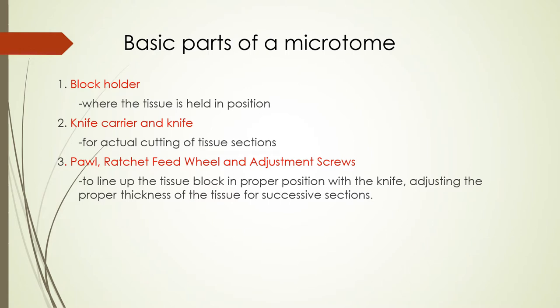Here we have a picture of the most common microtome used here and abroad — the famous rotary microtome. What are the basic parts of a microtome? First, we have the block holder, where the tissue block is held in position. Next, we have the knife carrier and knife, used for actual cutting of tissue sections. Then we have the pawl, the ratchet feed wheel, and the adjustment screws, which line up the tissue block in proper position with the knife and adjust the thickness for successive sections.